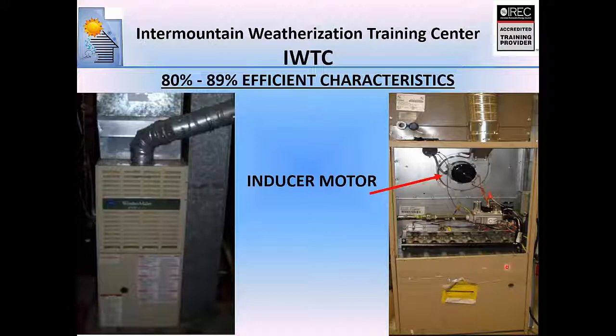So that's why these types of furnaces still need to be tested under worst case. If you get a CAZ that's negative 15, 20, you can backdraft these. I've seen it happen, and you'll see all the burn marks from the rollout happening, that type of stuff. If it's locked out due to a tripped rollout switch, there's probably a good chance that it's backdrafted. Okay.